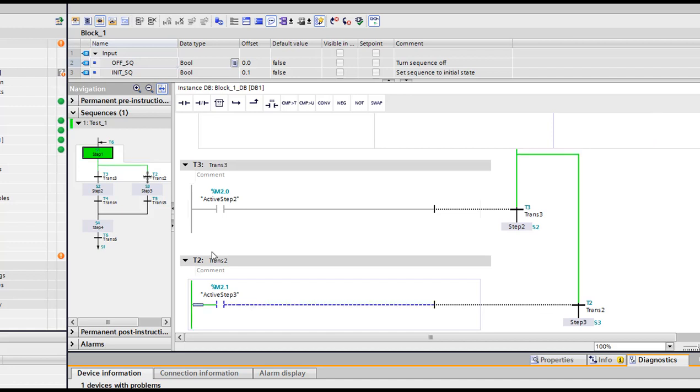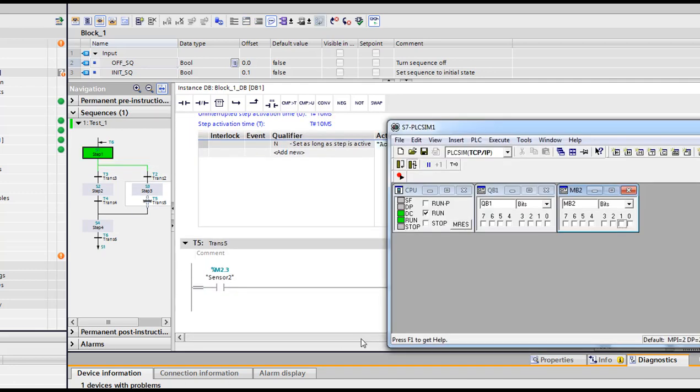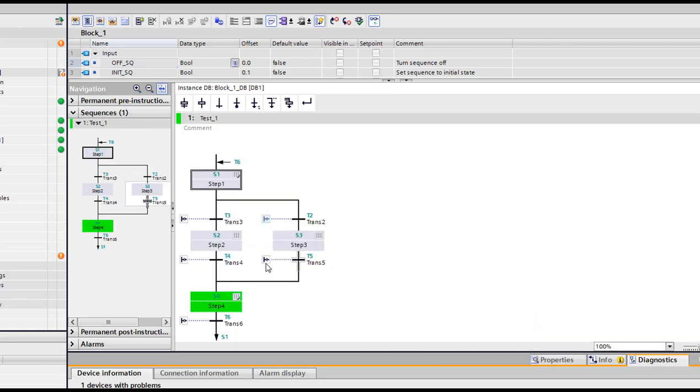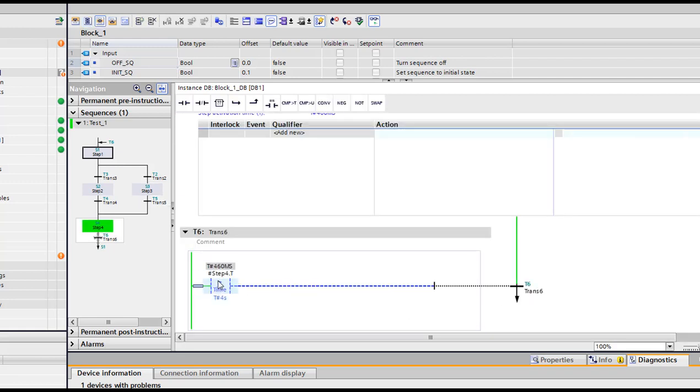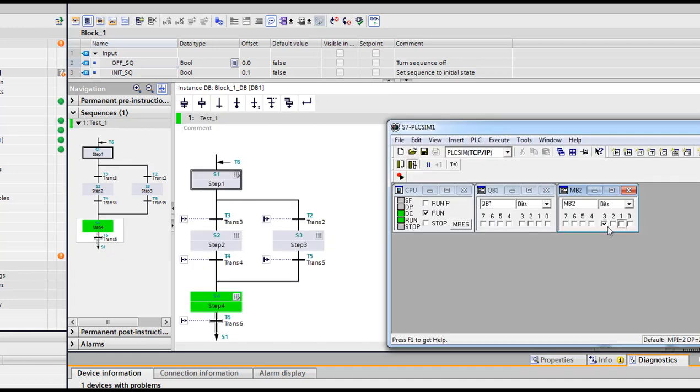We're gonna try it again. Here we have the M2.1 and M2.3, 1 and 3. As you can see, the program gets stuck here. It passes the 4 seconds I placed here, then it passes quickly from there and comes back again. As you can see, I checked before: 1 second, 2 seconds, 3, 4, then it comes back again. So don't make this mistake.